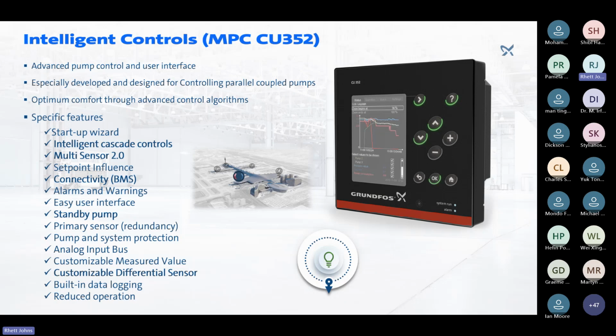So another way, and a part of the component for intelligent controls, would be to use a pump controller. As I mentioned earlier, what we want to do is run the pumps such that, if it's a high flow system and we would traditionally size up to a very, very large pump in order to match that top end required load, we can rather split the flow over several pumps. Using a pump controller, such as an MPC CU352, which is a multi-pump controller, you can start controlling multiple pumps in order to deliver your required flow in the system.